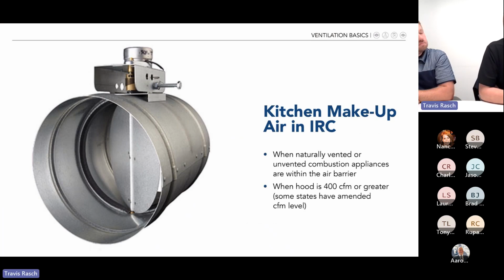I touched earlier on how we don't want to depressurize buildings, so I want to hit real quickly kitchen makeup air. As builders, I'm sure you've heard of this and have dealt with it. In the IRC and IMC, in the simplest form, if your state doesn't make an amendment, it says if your range hood is 400 CFM or greater, you need makeup air. Now, different states and cities will adjust this. Some moved it to 300, some moved it to 600. Some say you have to make up all of it, others say you only have to make up the amount over 400. So you should really check with your local code official on exactly what you need to do.